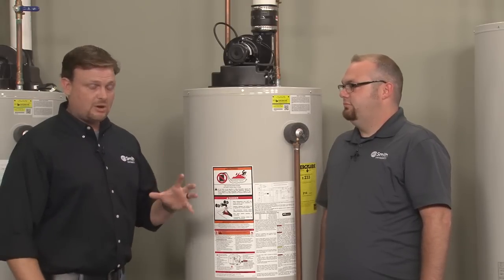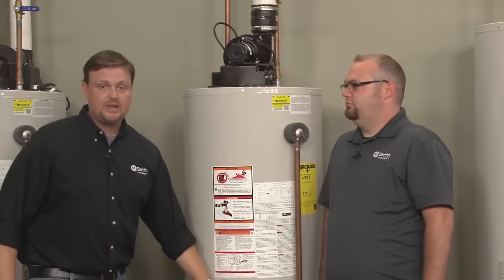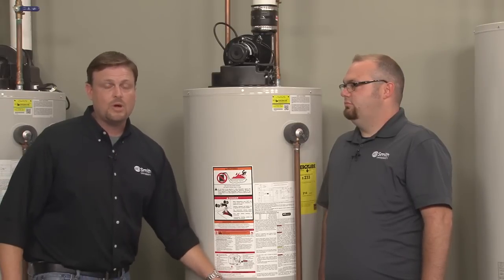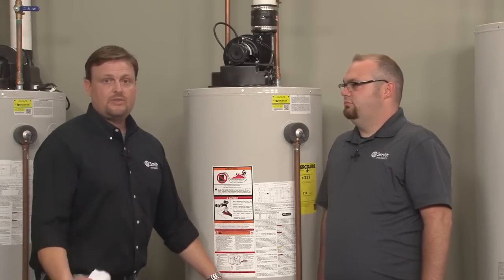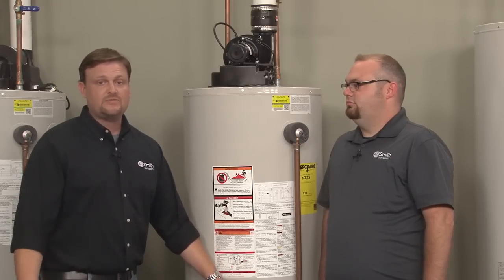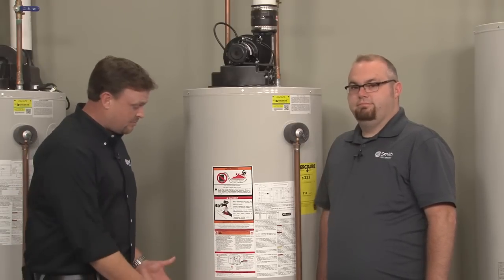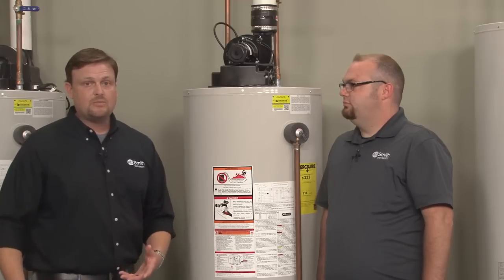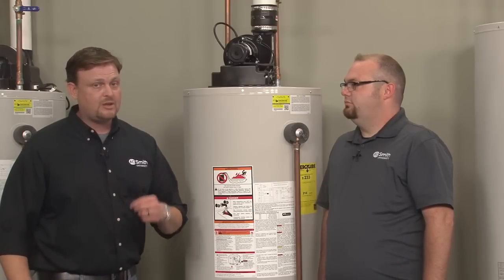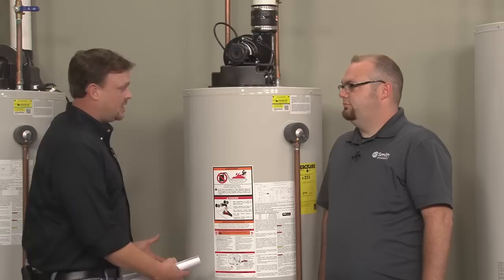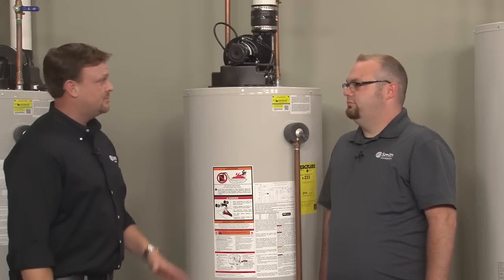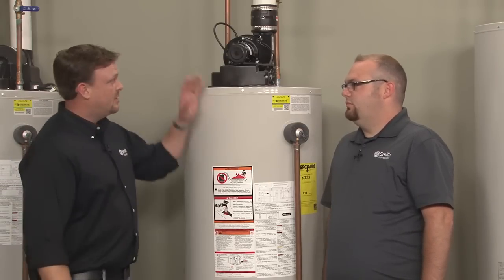That makes that complete circuit. Once it sees the circuit, the igniter will then warm up for 17 seconds. Once it reaches 17 seconds, the gas valve opens up. We dump gas into the burner chamber and light the burner. We have 4 seconds to see that flame. Once we see the flame, we start heating the water. We come up to temperature. The gas goes off.